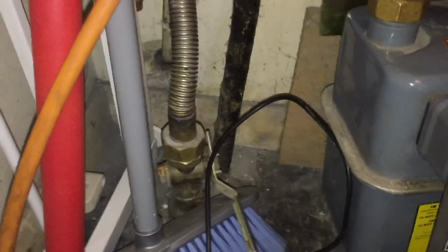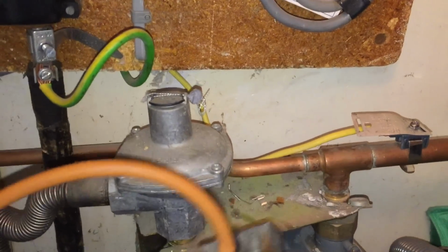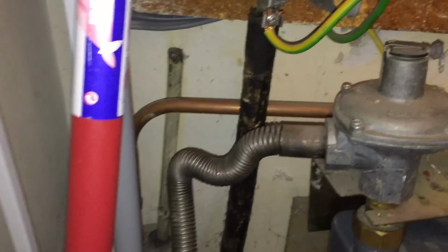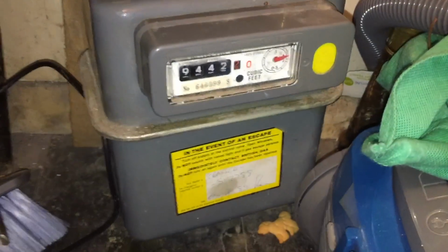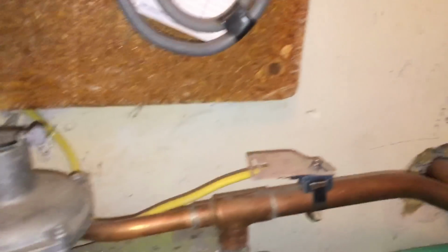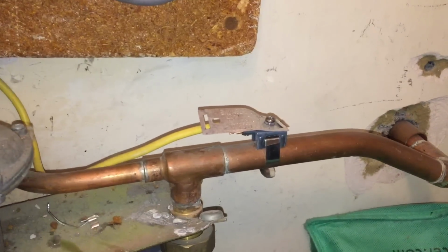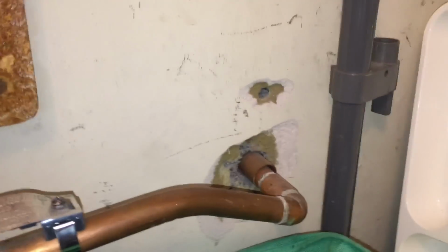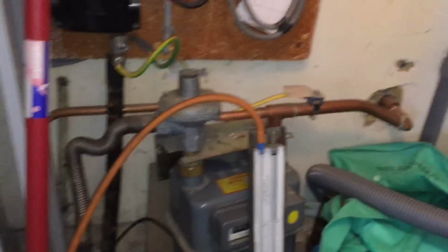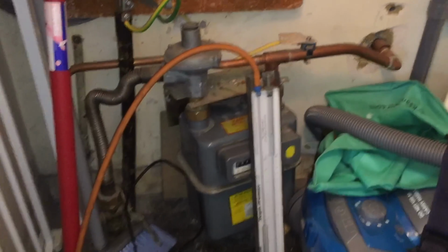Okay, so visuals on the meter. ECV's not labelled. Governor is sealed. Too close to the main. Incorrect telephone number. We have got an earth clamp. It is sleeved, but it's not sealed. Gas pipe touching the main there. Look. Brilliant. So anyway, let's get on and find out why this boiler's not working.